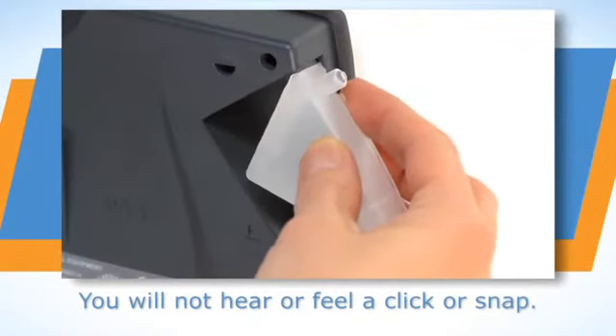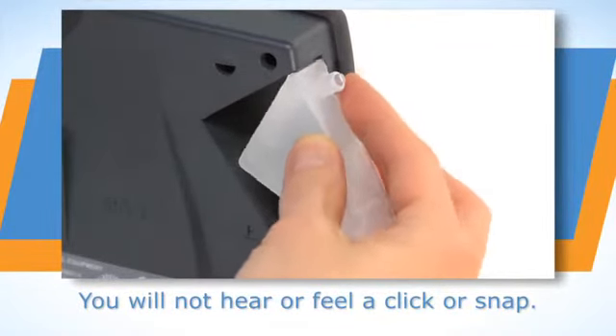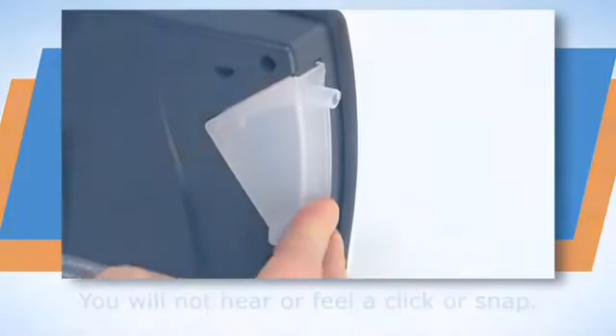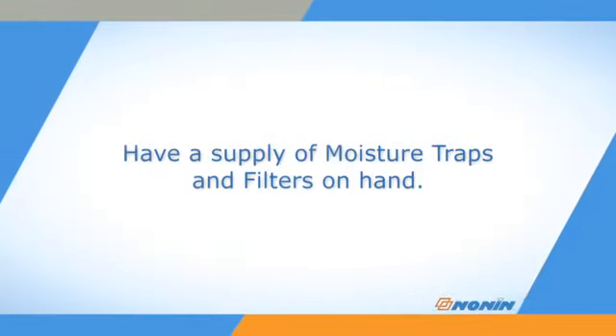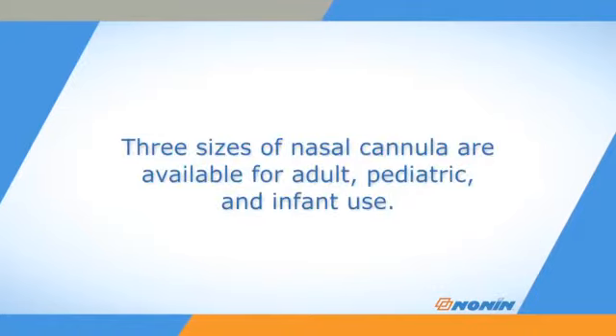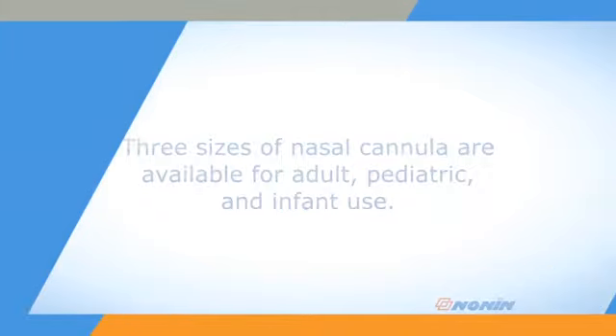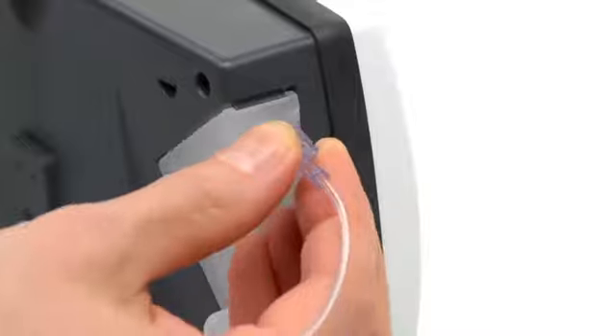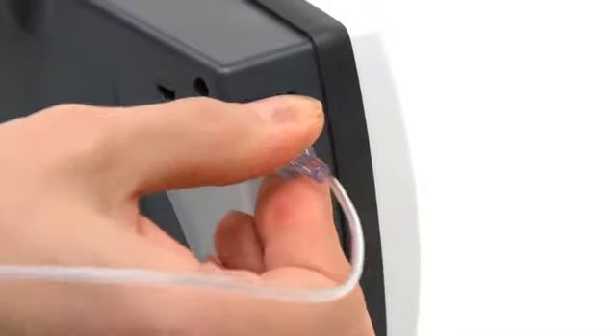Use the marks in the trap opening on the monitor as a guide to properly insert the trap. It will not snap into place. Have a supply of replacement moisture traps and filters on hand. 3 sizes of nasal cannula are available for adult, pediatric, and infant use. Place the nasal cannula and snugly attach the sample line to the moisture trap using the luer lock stem on the trap.